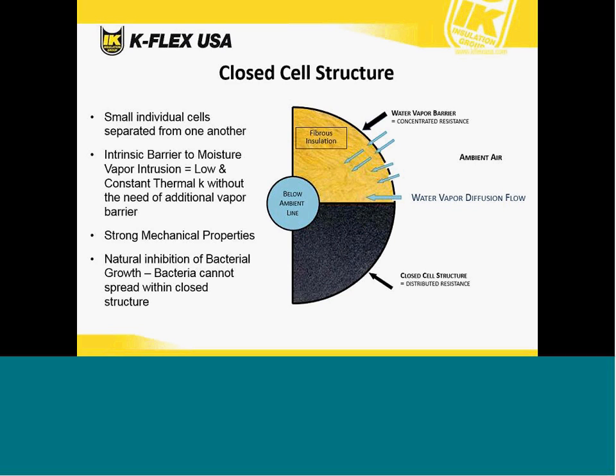Bacteria can't spread within a closed cell structure because it's physically trapped within one cell and it can't penetrate through the cell walls. It's also something that we like to call distributed resistance. With a closed cell type of insulation, if there is a slight tear or rip in the outer jacket or the outer skin, there are millions of closed cells behind that skin providing protection from water vapor penetrating through the material. With fibrous or open cell insulation systems, if that jacket is penetrated and there's a point of failure, moisture can then penetrate through that point of failure and migrate through the entire system without distributed resistance behind it.